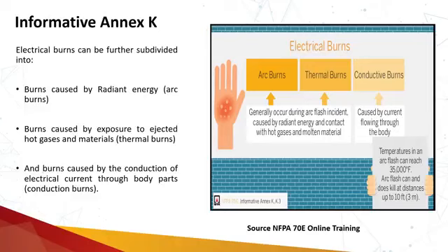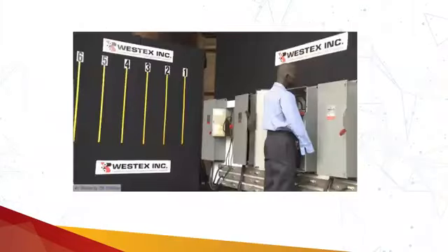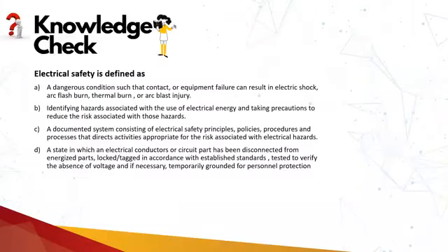If not, then how can these two be prevented? If you are performing some justified and authorized work on the live system, then these can be prevented by wearing appropriate PPE which is arc rated. Okay, so if you are using arc rated personal protective equipment, then this arc burn and the thermal burn can be mitigated. Any questions up till now on these types of hazards?